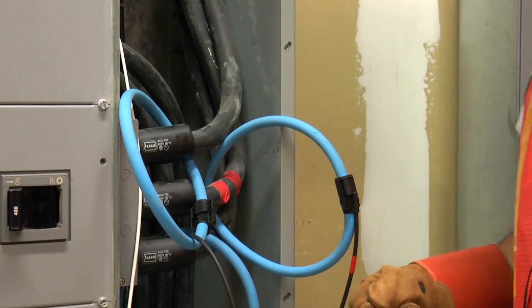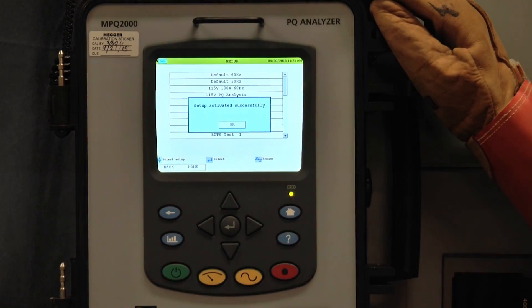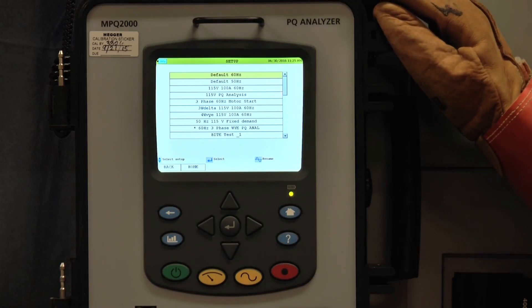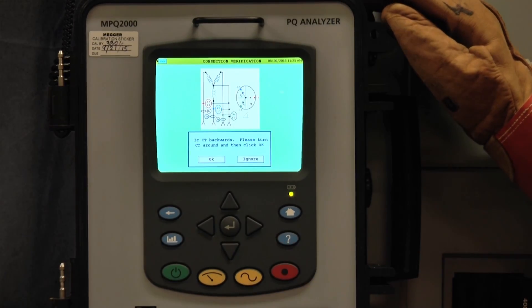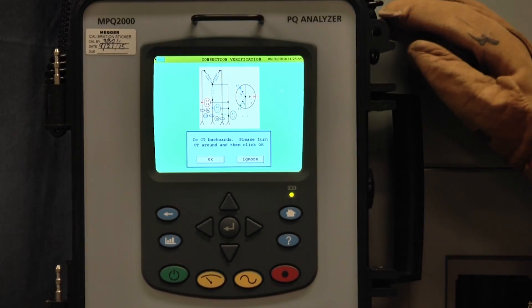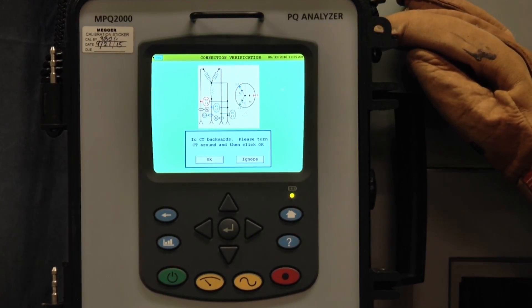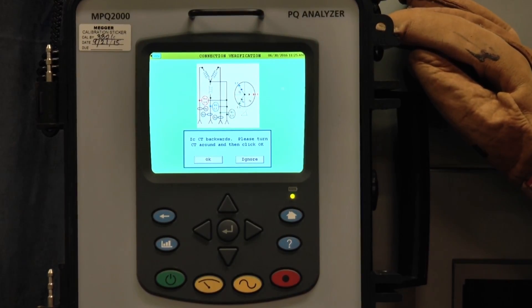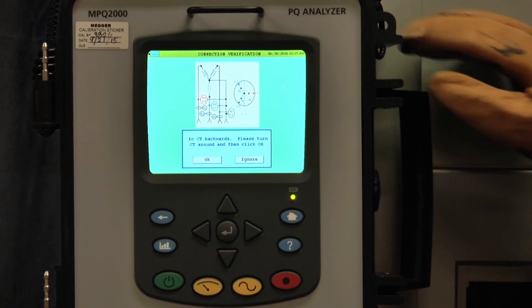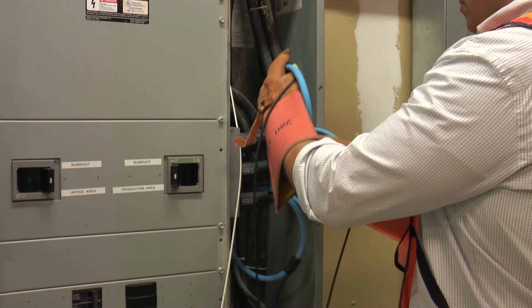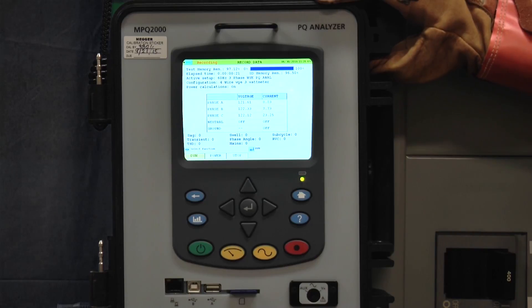Simply connect the unit. Select the desired setup configuration. Start the recording. The unit will let you know if it is not connected properly. You can see that the phase C current clamp is backwards. Let's turn it around. The unit is now recording.